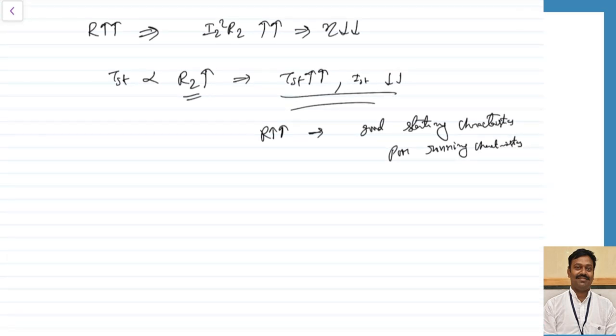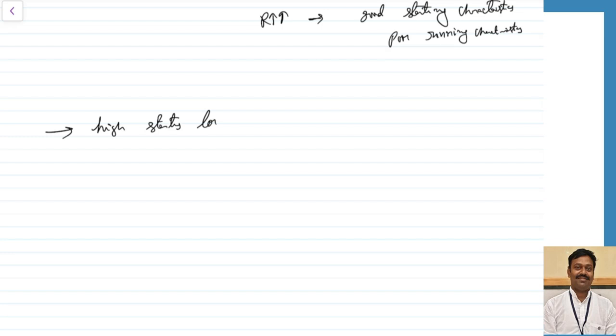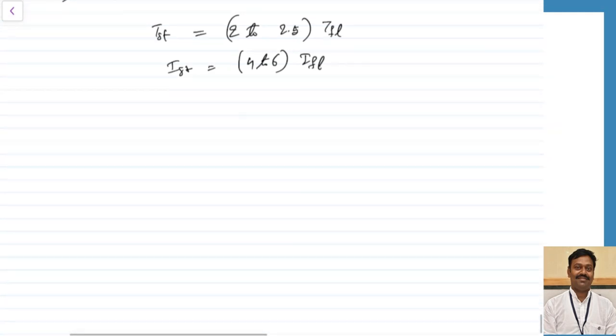If we can combine the features of these two, we can get better performance — meaning very good starting characteristics and very good running characteristics. In order to provide a high starting torque with a low starting current, we go for the double cage induction motor. In the double cage induction motor, the starting torque varies from 2 to 2.5 times the full load torque, whereas the starting current is only 4 to 6 times the full load current because of the large value of resistance.